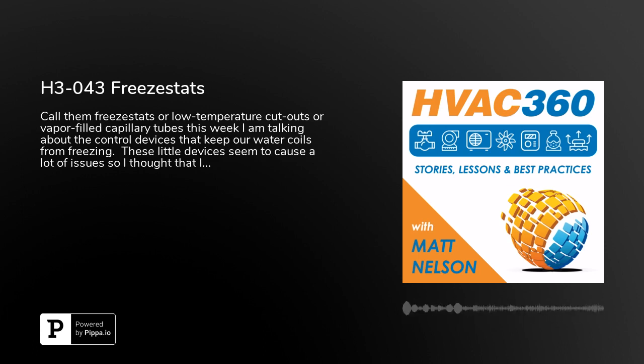So, what's important to know about freezestats, and why does everybody need to know more information about them? Freezestats, improperly applied, are going to have nuisance trips, and this is a bad thing because the freezestat in and of itself does the perfect job. It's the right technology, obviously when installed properly, and it really does the job and is really reliable. But if it's installed improperly, or there's something wrong with the design where you're constantly tripping the freezestat, now you have the building operator losing faith in this. It's the whole boy who cried wolf syndrome.